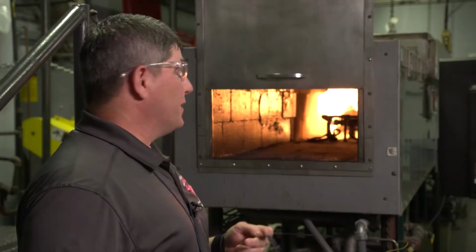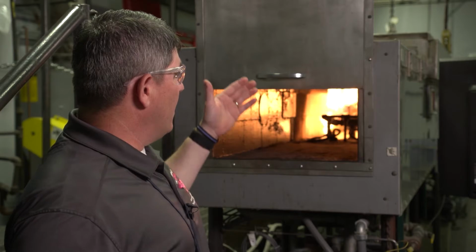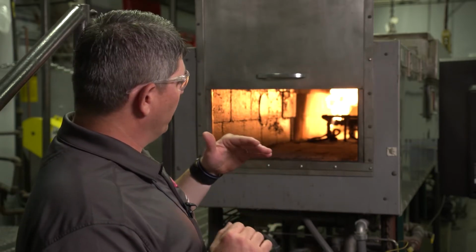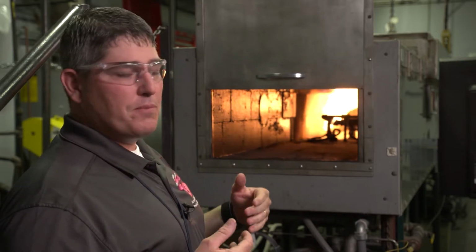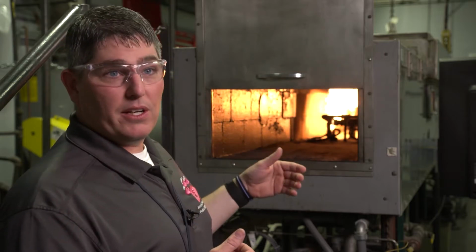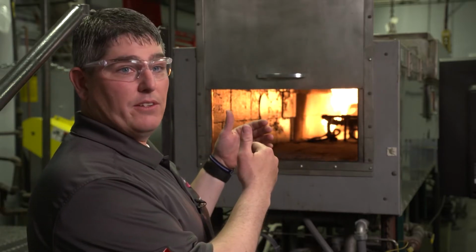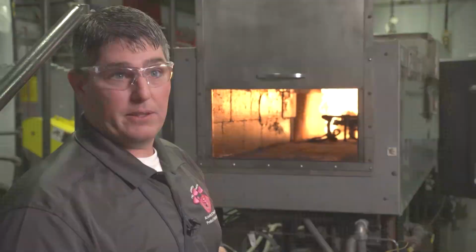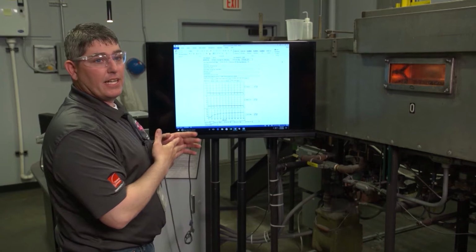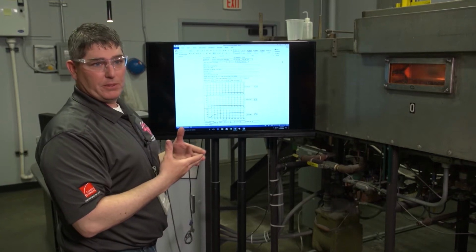Today we're using the ASTM E84 Steiner tunnel to assess the surface burning characteristics of our mineral wool insulation. In the E84 tunnel test, the sample is top loaded in a ceiling orientation so that when the flames come up, they hit the bottom of the sample, just like on every sample, even comparison samples. From there, it depends on what the product is made of. We'll then determine how far the flame front travels down the surface of the material. These are the results from the ASTM E84 Steiner tunnel test. We get a flame spread index and a smoke developed index, and those help us meet the codes.